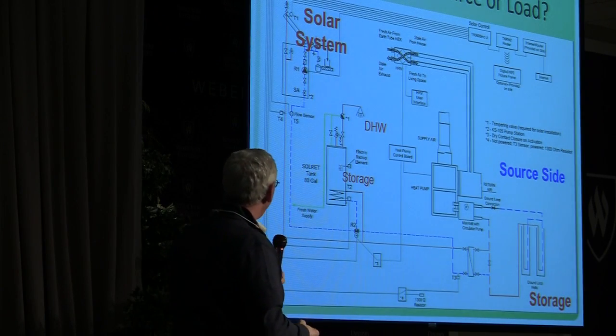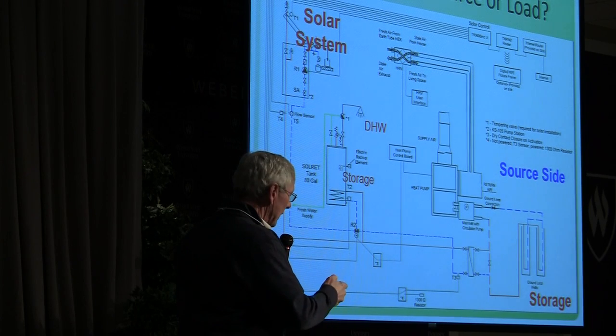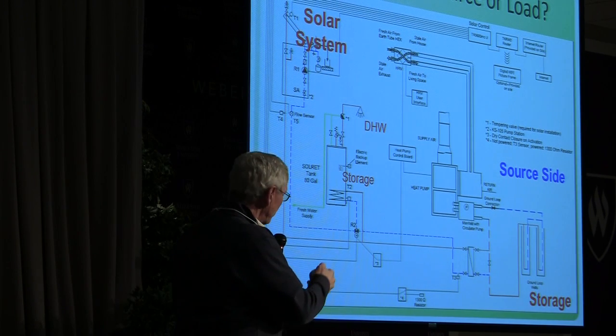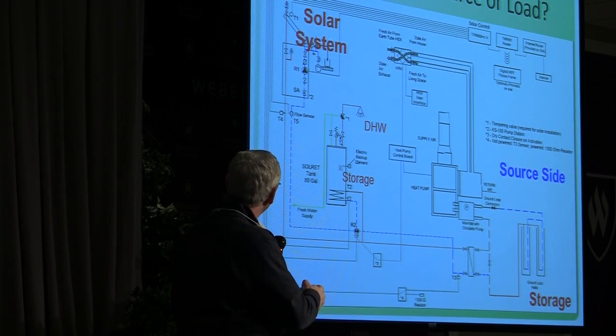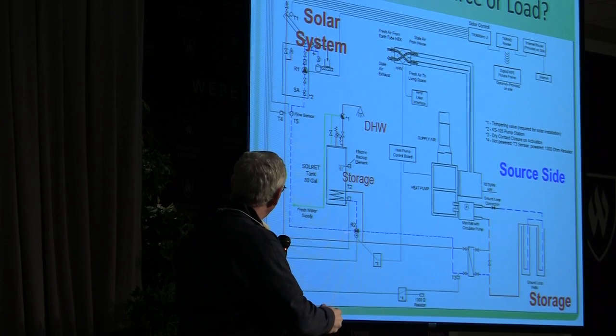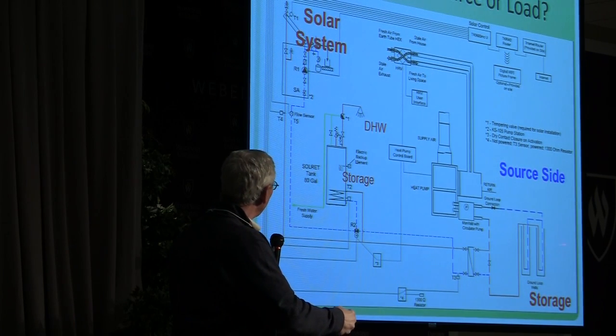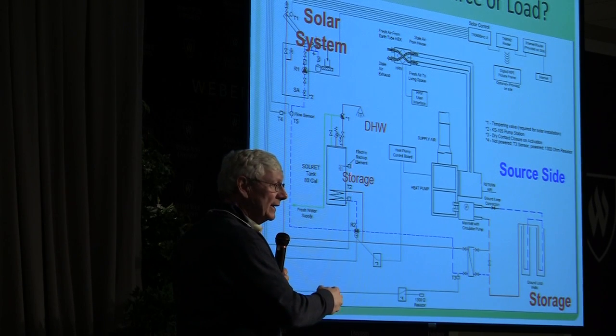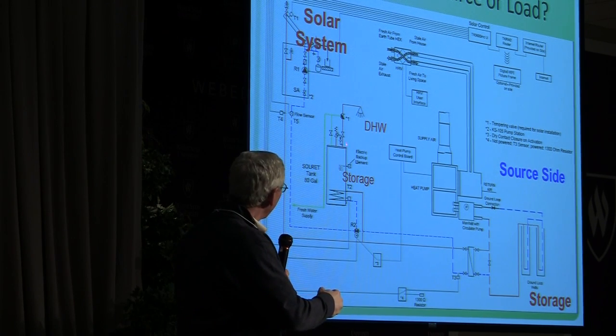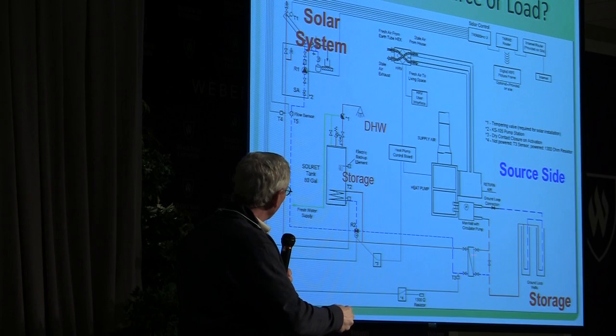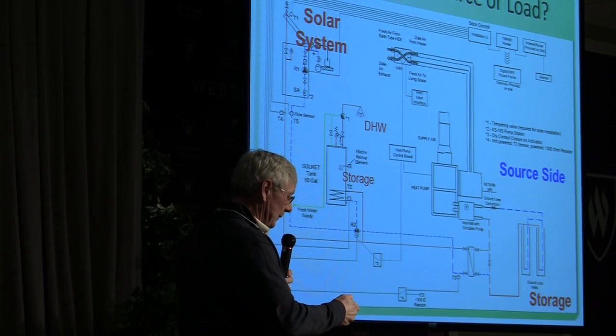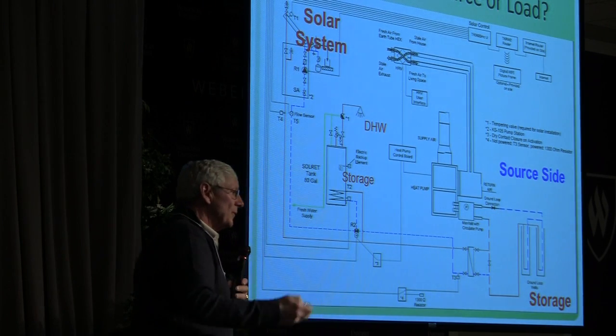A little less clear drawing, but here's one for the source side, where the solar system is being used to supplement the ground source. It also has a direct tie-in to the load side for domestic hot water. But generally, we're putting energy into the ground if we have too much available to us.